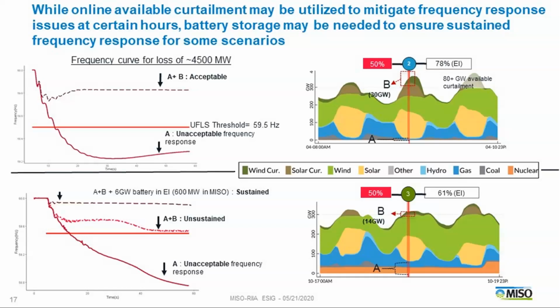We also looked at deploying battery technology along with frequency-enabled renewable plants to bring frequency back to a stable level, and it worked out quite well. Surprisingly to me, it took a relatively small amount of change to the system to maintain good frequency performance. The conclusion is that from MISO's perspective, frequency response isn't likely to be a major problem. There's additional work needed on potential islanding events or other things that would make the system look smaller than it is today, but from an interconnection-wide standpoint, we can get to pretty high amounts, and the solutions are relatively straightforward once we start seeing issues.